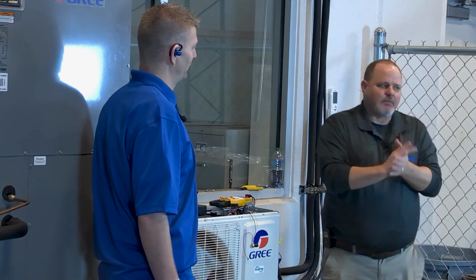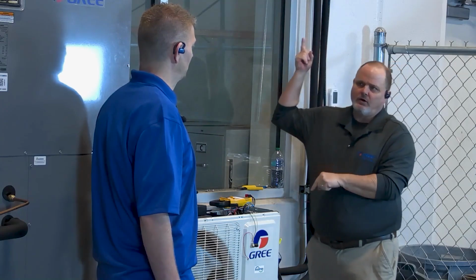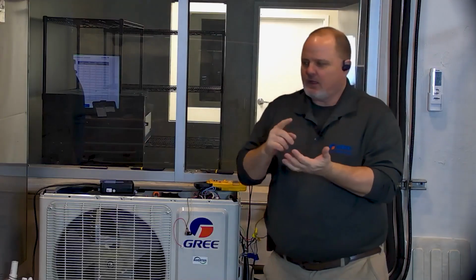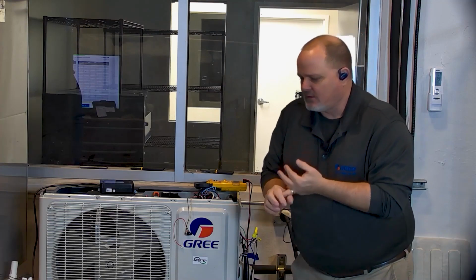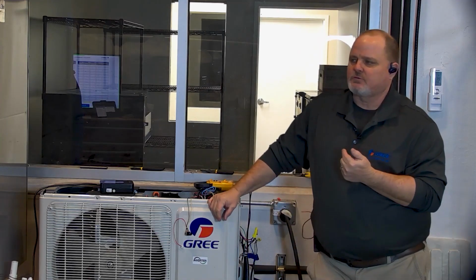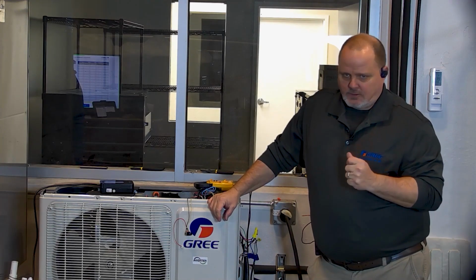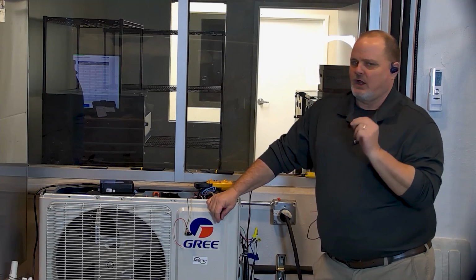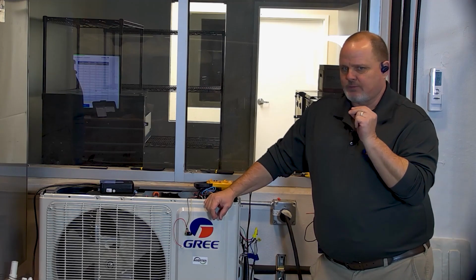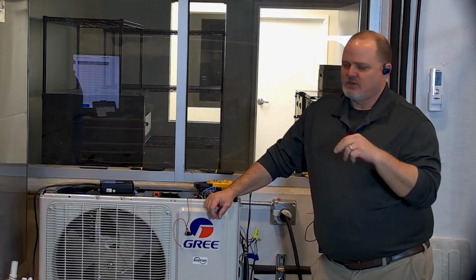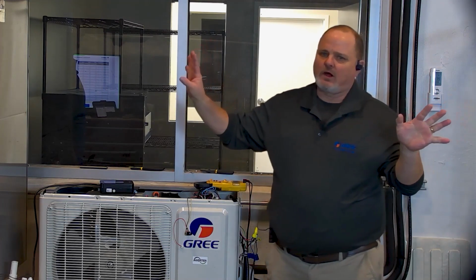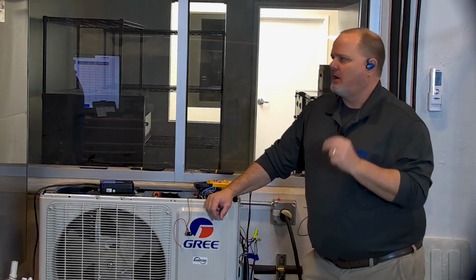So don't stop there. You're not done yet, because you could have a bad 14-4 wire going in between. Just about every one of our guys in tech support has talked about this before. You can take an ohm meter to that 14-4 wire and ohm it out, and you will think there is absolutely nothing wrong with it. You can disconnect the 4 wires outside, disconnect the 4 wires inside, ohm between them, and it doesn't show any short between the wires. You think that cable is 100% not a problem.